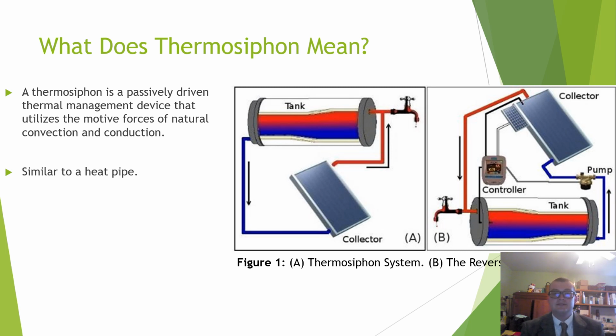Figure 1b shows the same cycle, but reversed. Since the evaporator is higher than the condenser, the system needs a pump, and because it needs a pump, it also needs a controller. Figure 1a is a thermosyphon, but figure 1b is not, because it requires a pump and external energy to fuel the system.